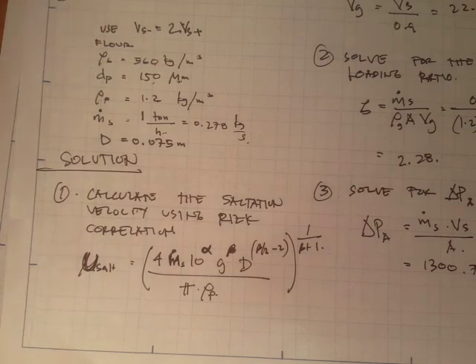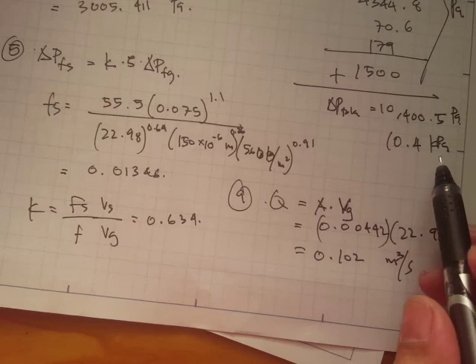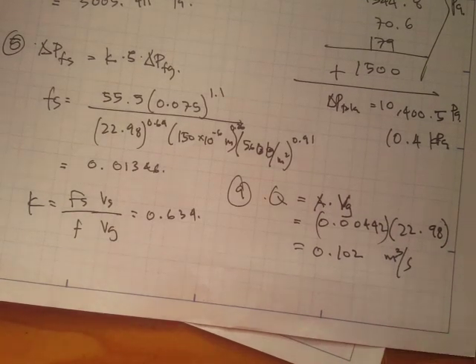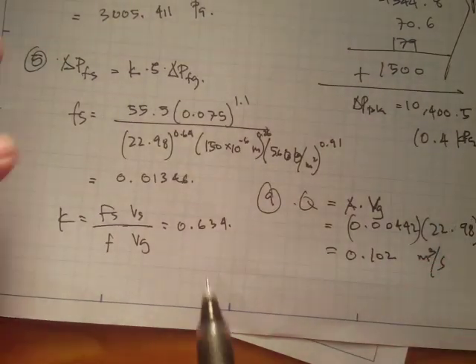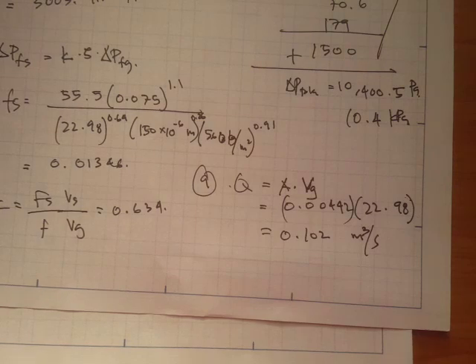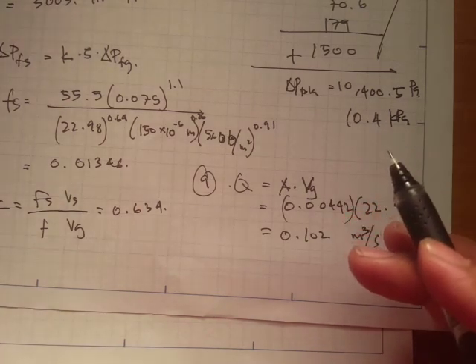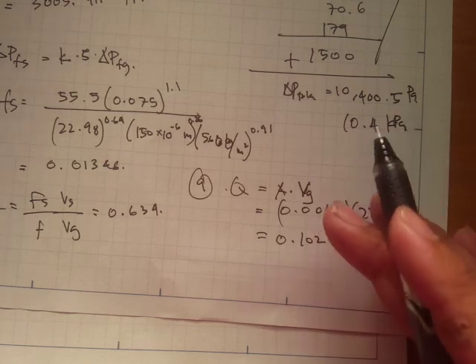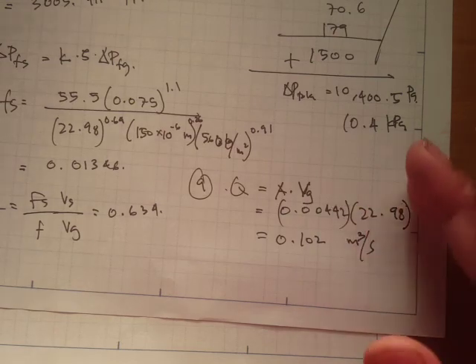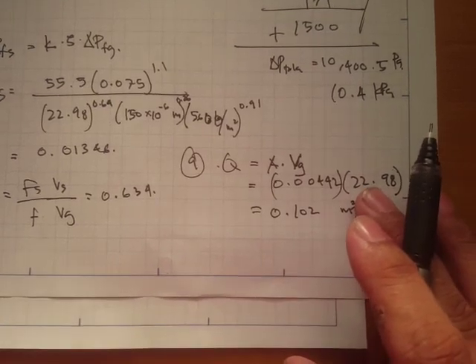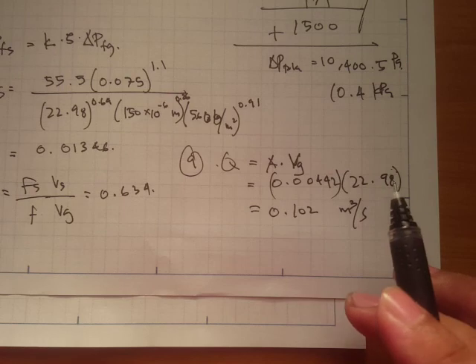Okay, so just a practical question. If we obtain the value of 10.4 kilopascals for the static pressure and the flow rate of 0.102 meters cubed per second, is it going to be the actual conditions? Of course, in practice probably not. So it's going to be a range, and you have to be ready to tweak the system a little bit or apply engineering judgment about the selection of the fans, or maybe you would like to increase the pressure or increase the specs. And of course there are going to be advantages and disadvantages. Again, that's going to be a range, and it's going to be a decision for the designers.